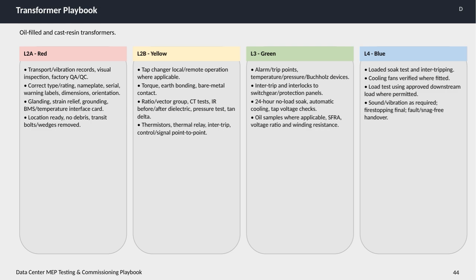Finally, level 4, denoted by blue, is about putting the transformer under full operational conditions. A loaded soak test is conducted along with verification of cooling fans where fitted. Load testing uses approved downstream loads when permitted. Sound and vibration assessments are carried out as required. Final fire stopping measures are completed, and the process concludes with fault and snag-free handover, ready for full system integration. Together, these levels ensure that transformers are tested thoroughly at every stage, from delivery through to full commissioning, supporting reliable and efficient data center operations.